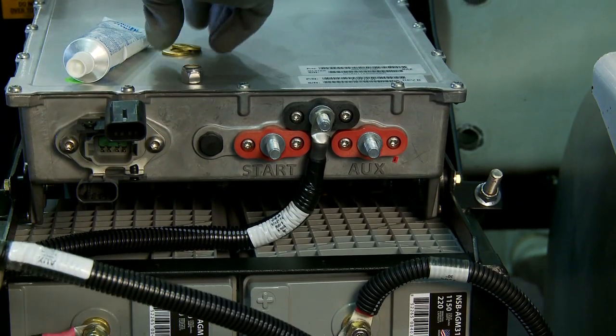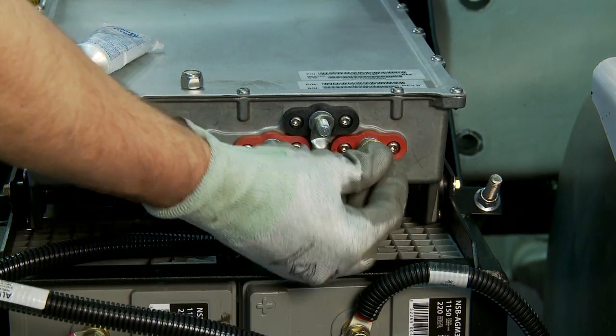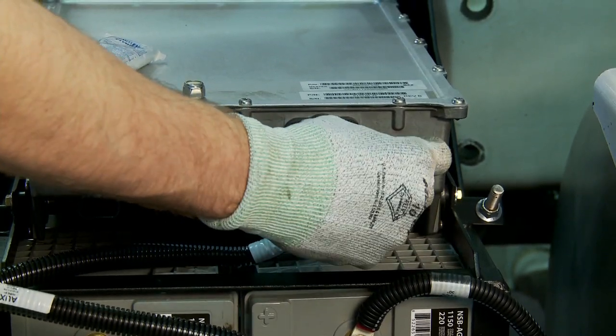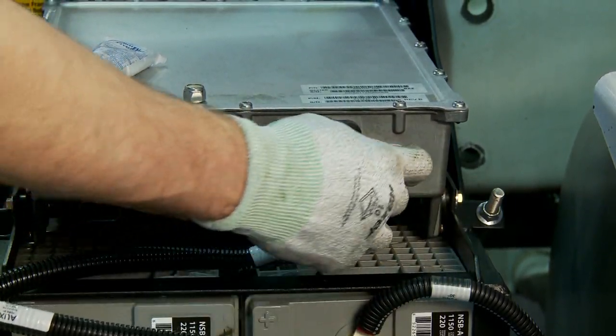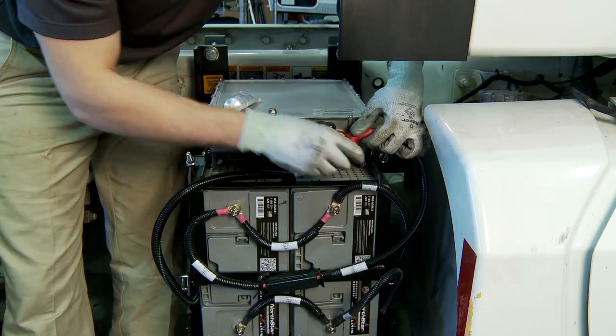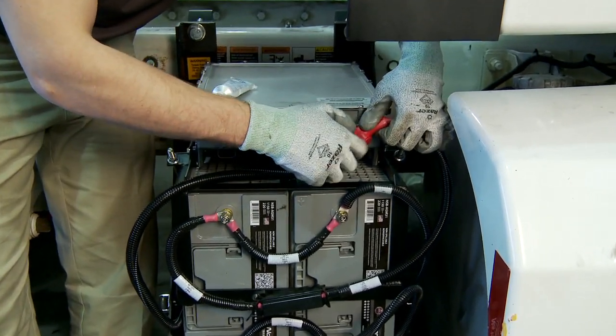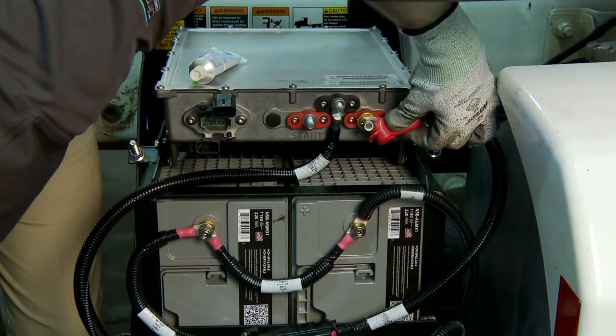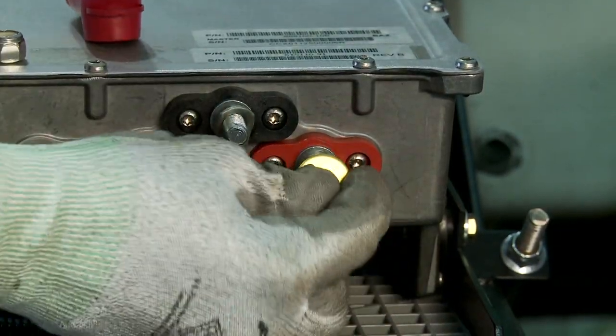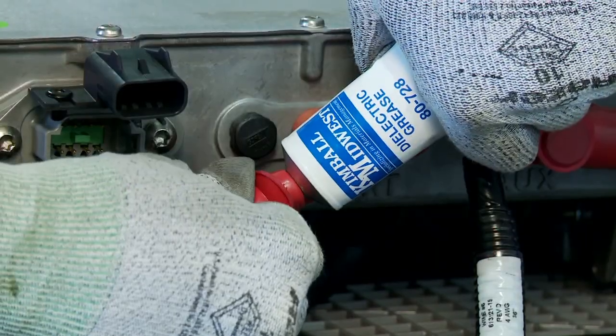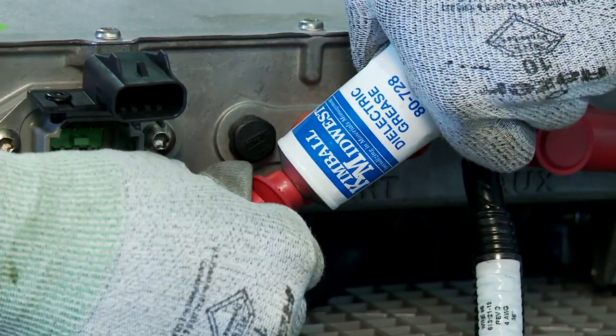When connecting the power to the PMM for the first time, make certain that the auxiliary batteries are fully charged and connected first to the PMM. Connecting the PMM to discharged batteries will prevent successful system commissioning. Use the PMM cable boot and corrosion control kit when connecting the truck battery cables to the PMM, and use dielectric grease to prevent corrosion.